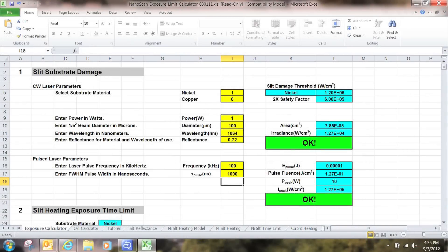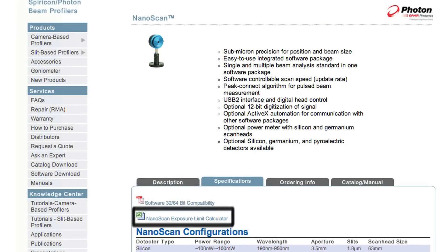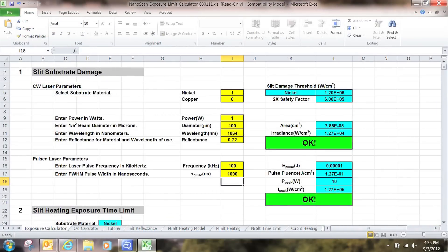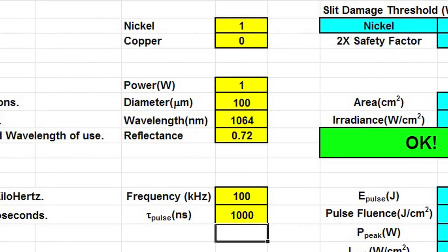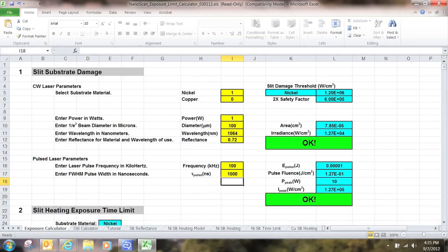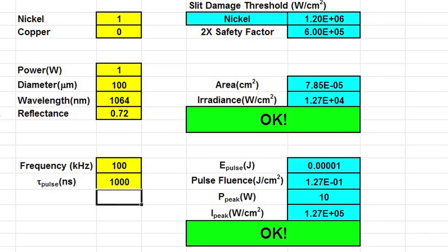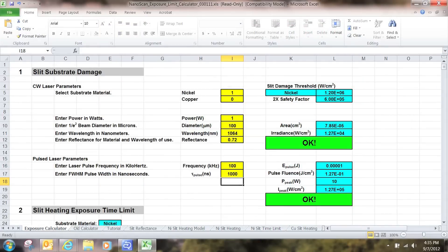In addition to the operating space charts, there's also a nanoscan exposure limit calculator. This is an Excel spreadsheet available off the Ophir Spiricon website that you can use to enter the parameters of your laser and of the nanoscan that you're using, and it will compute whether you're in a safe operating range or a cautionary range or outside of the safe operating range of that particular nanoscan.